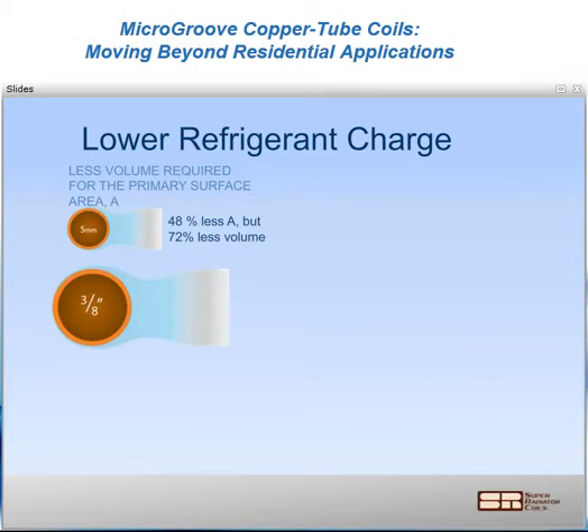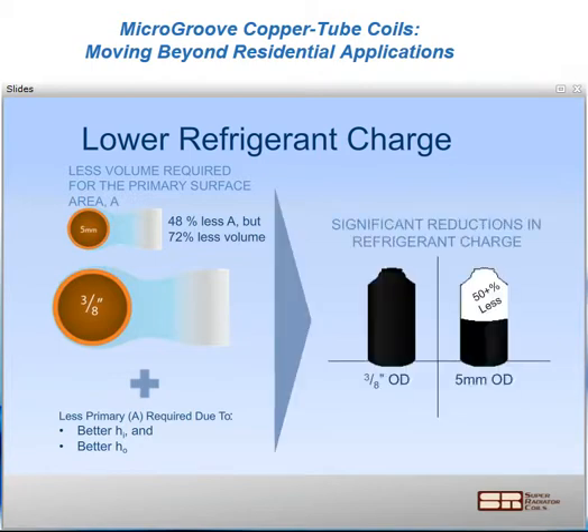A couple other things to point out. Louis talked about the refrigerant charge, and I just wanted to expand on that for a moment. Geometry is in our favor, and this is just simple math of geometry. When we move from a 3/8 to a 5 millimeter, our primary surface area has reduced 48%, but our volume has reduced 72%. Now, if you recall, Louis mentioned 50% plus refrigerant charge reductions. Well, how do we get there? Again, it's the heat transfer coefficients. So when you combine geometry in our favor with better coefficients, that's when we see those really powerful reductions. When does this apply? Customers looking at propane as a refrigerant, really important.